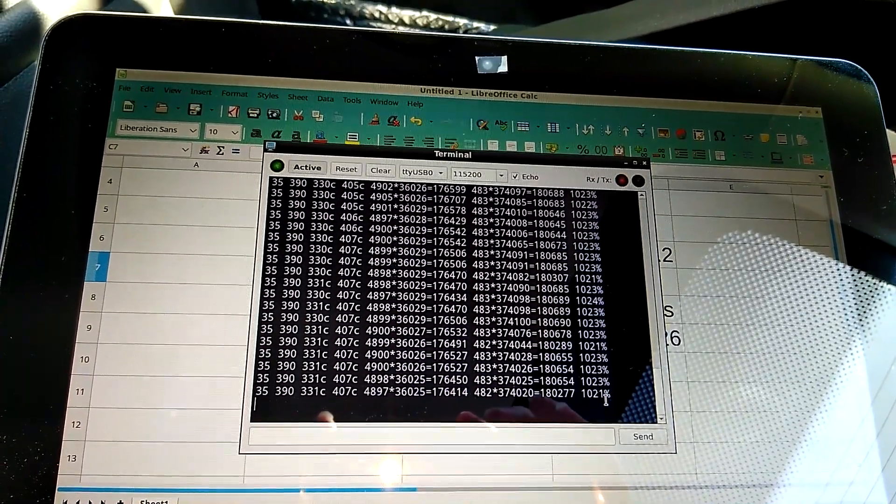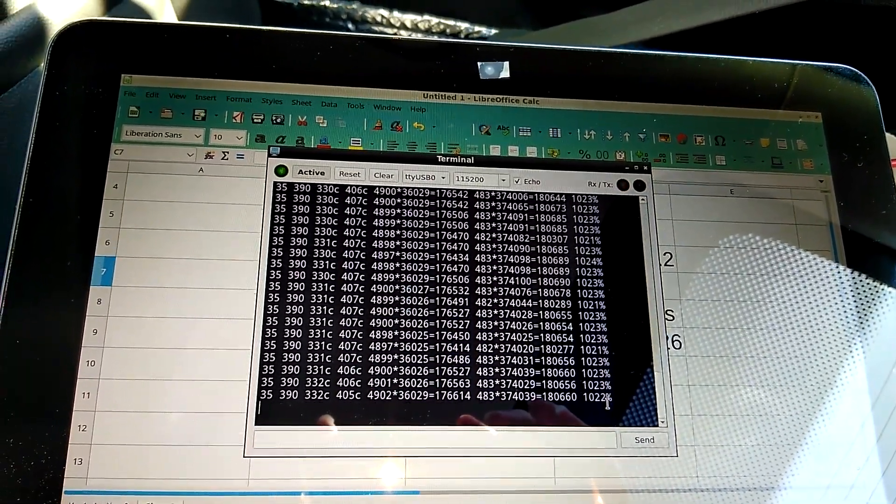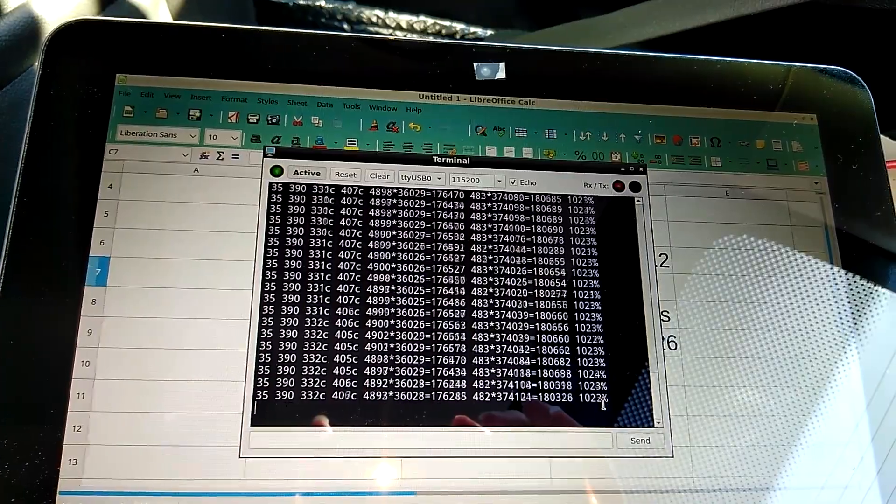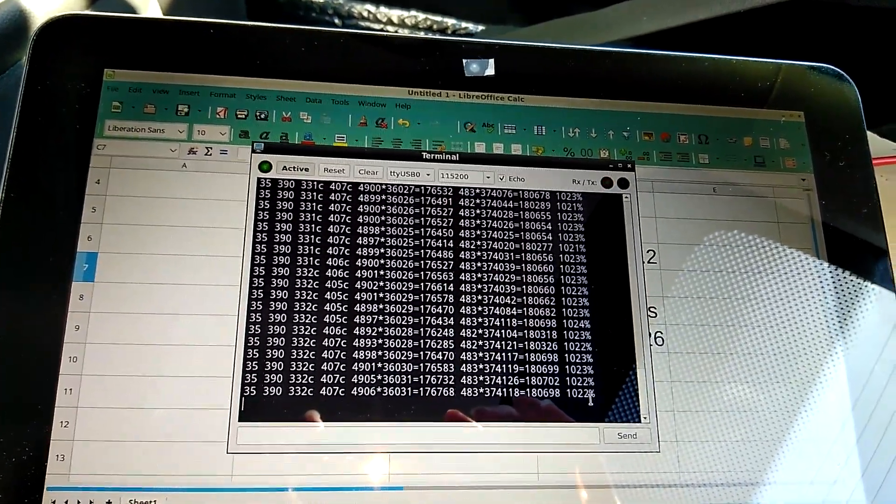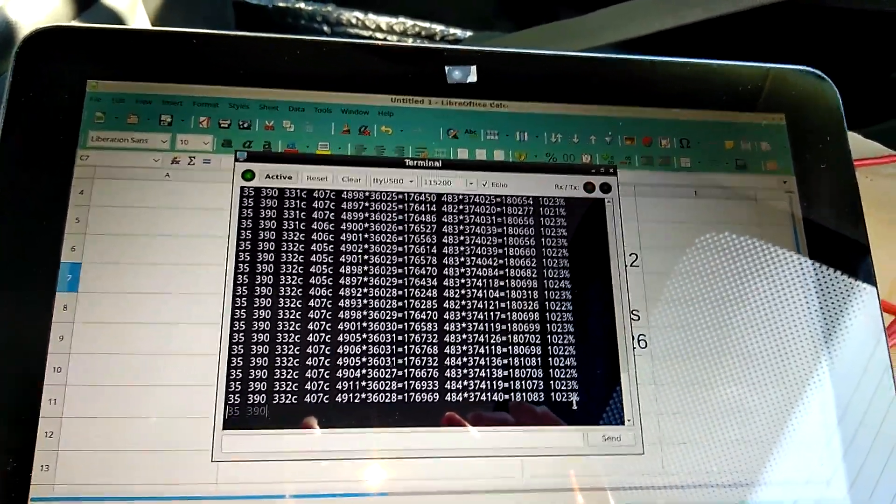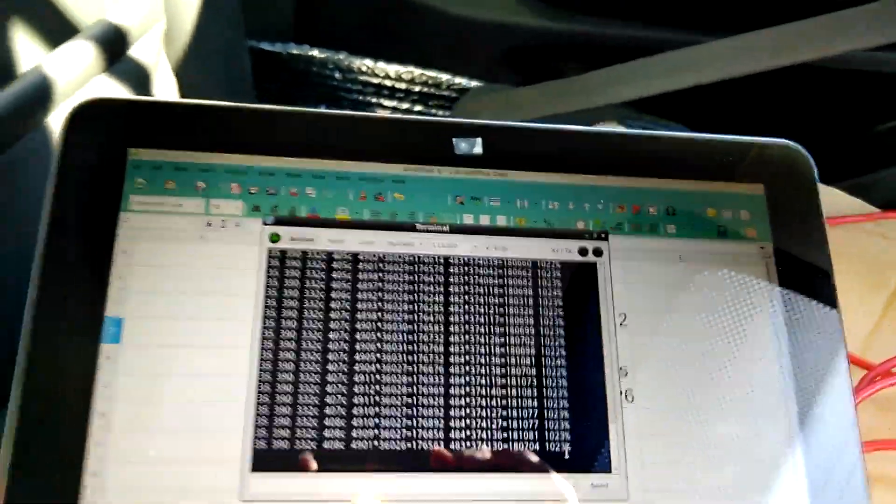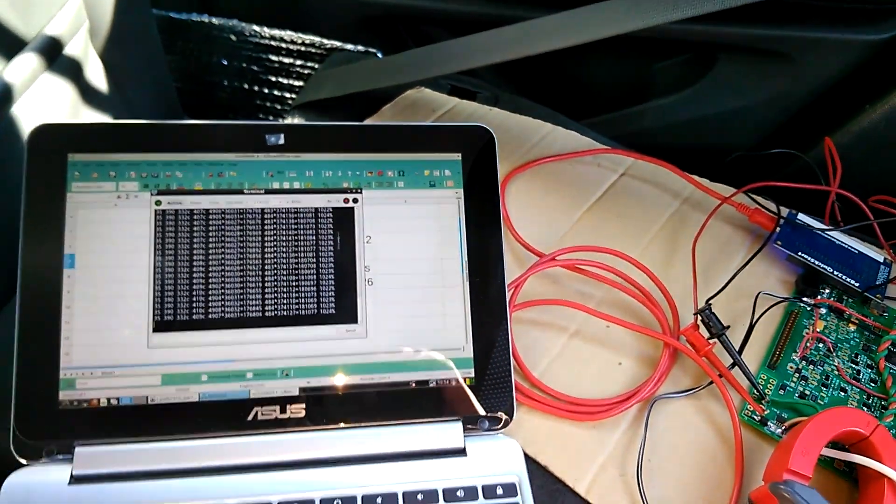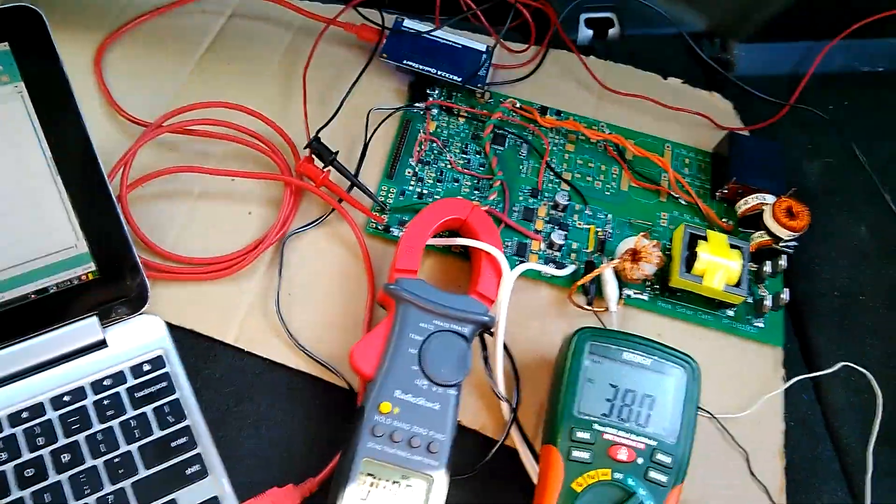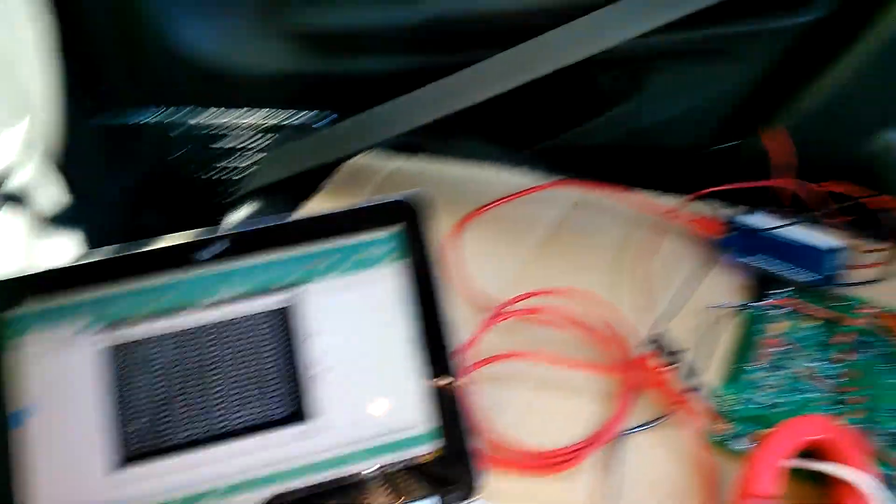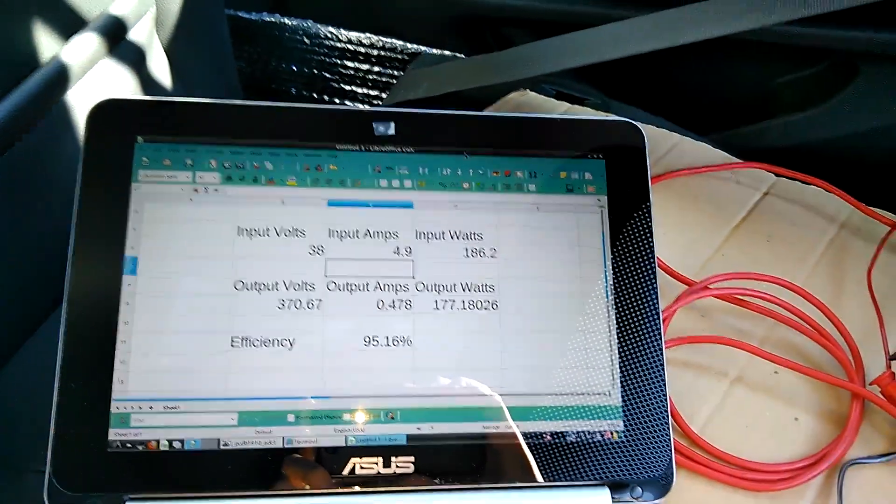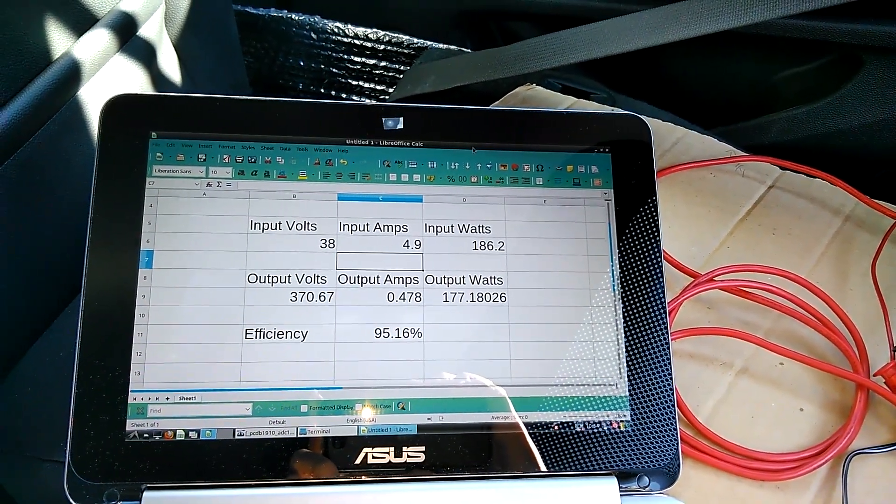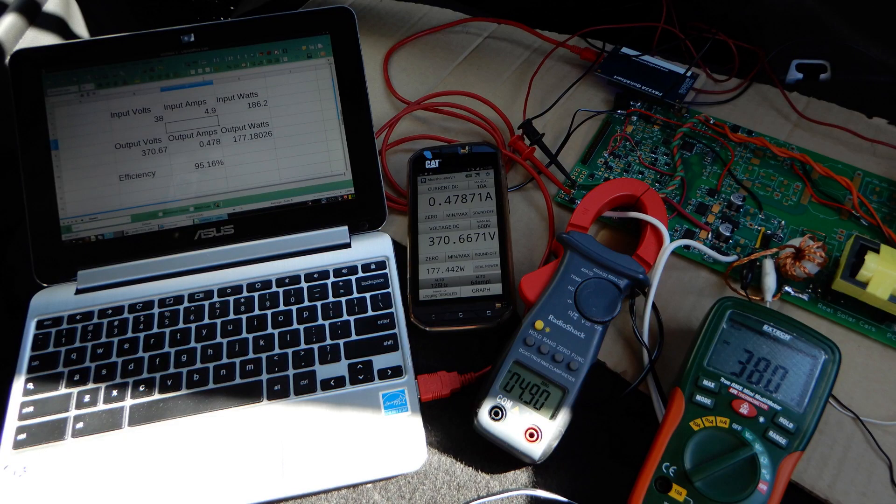As you can see, it's reading 102.3 percent efficiency, which is of course not correct. But I have calculated the efficiency using my external metering and find approximately 95 percent efficiency out of this converter, which is quite good.